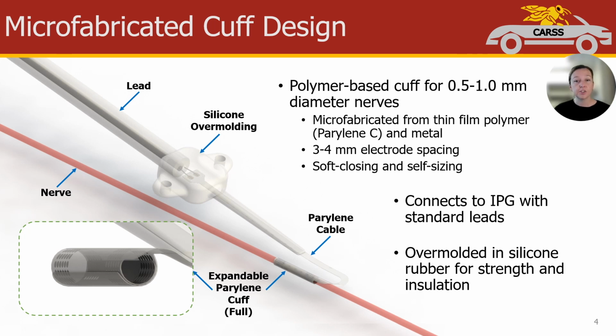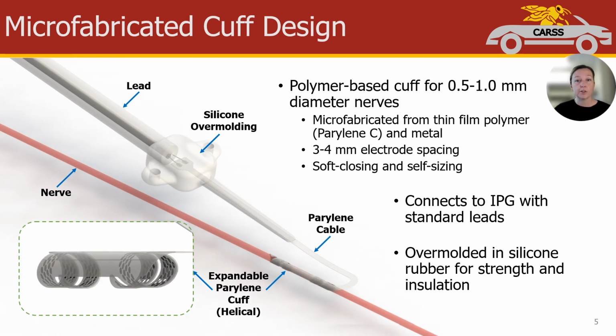We designed 2 versions of the expandable Parylene cuff. The full cuff, shown here, has Parylene insulation between the electrodes, resulting in a mechanically robust cuff. We also have a helical design, shown here, which has 2 helical electrodes with no insulation between them except for 1 small bridge. This design is much more flexible and likely better for more tortuous nerves. We have chosen to evaluate both of these options to allow for more user flexibility.